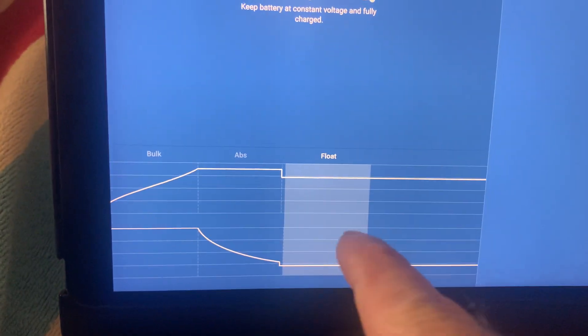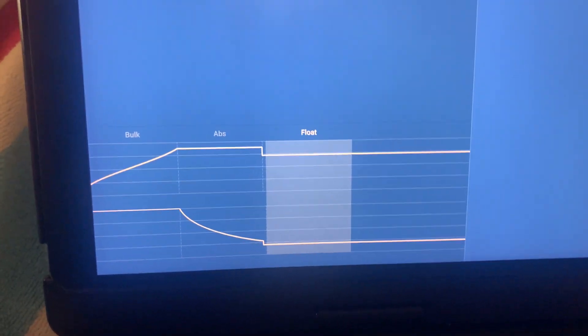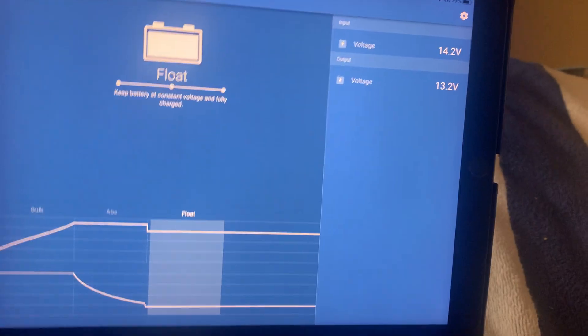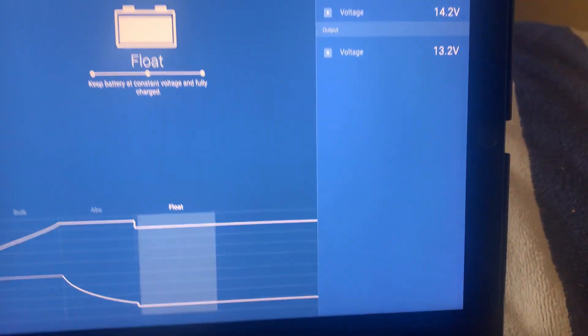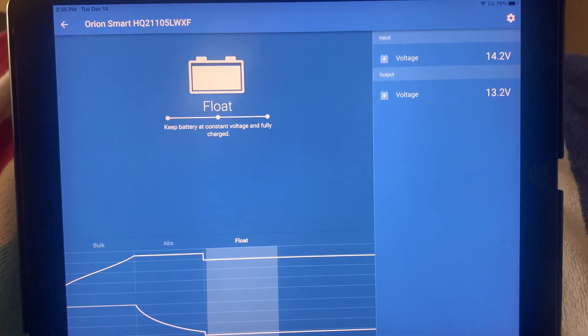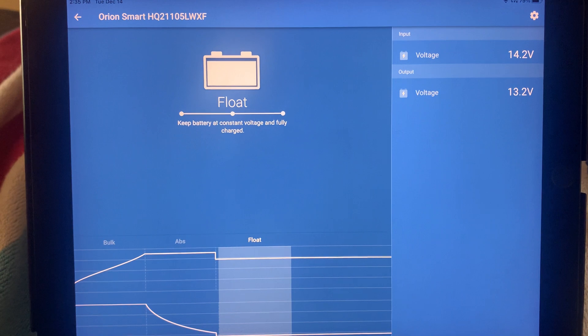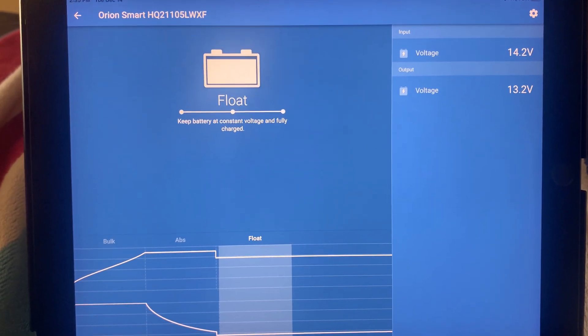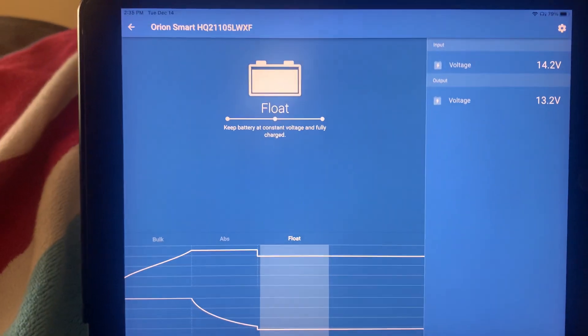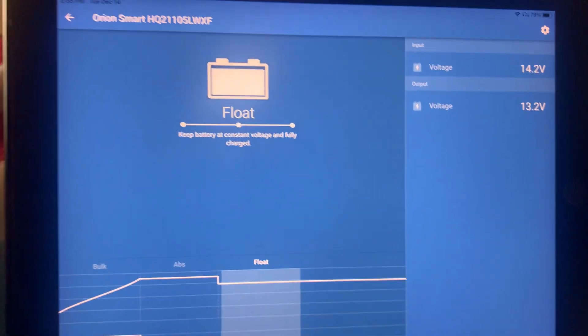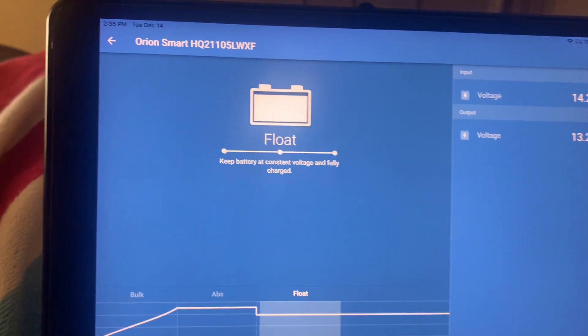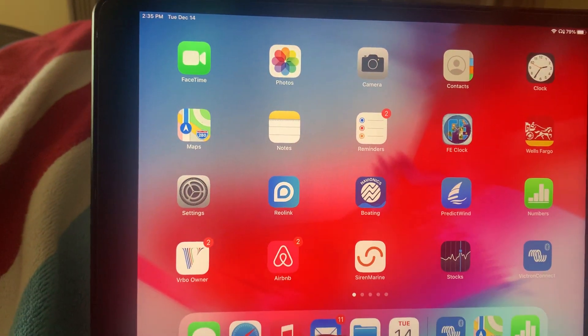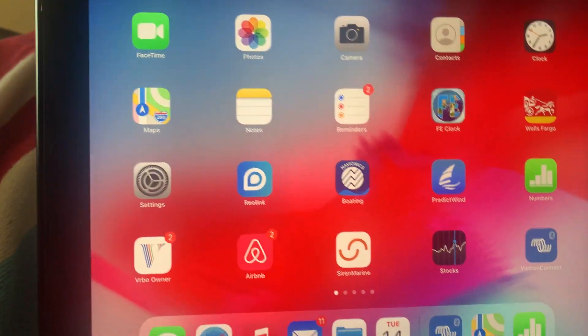Yeah, he's in float now. Perfect. Absolutely perfect. So I can keep the batteries dedicated for 12-volt topped up nicely with a very minimal draw on the new lithium battery to keep those guys topped up.